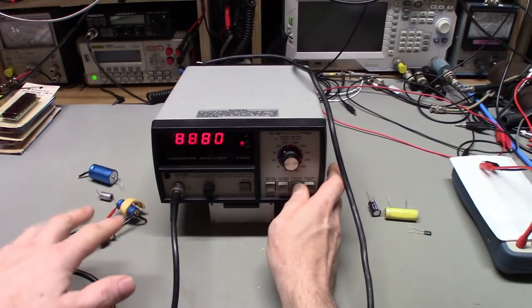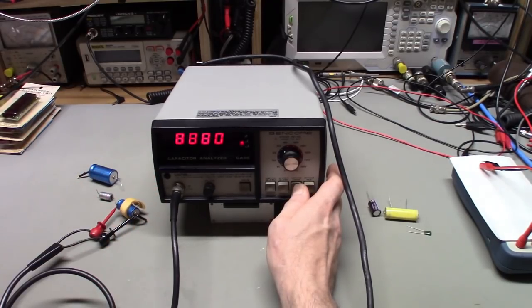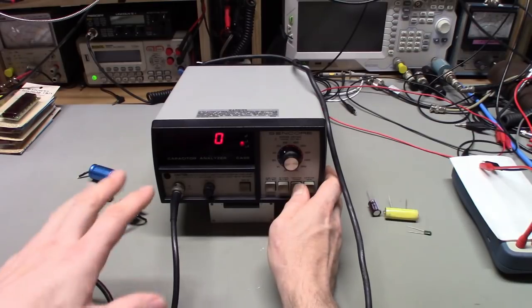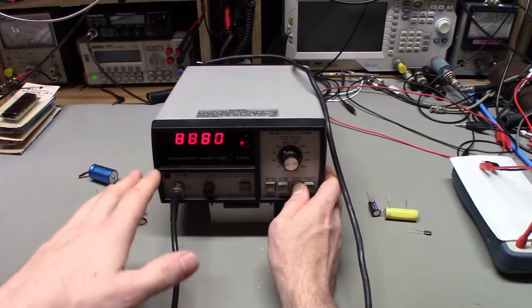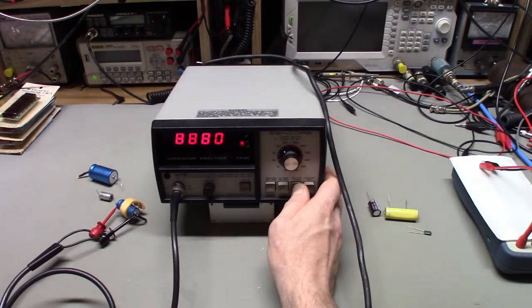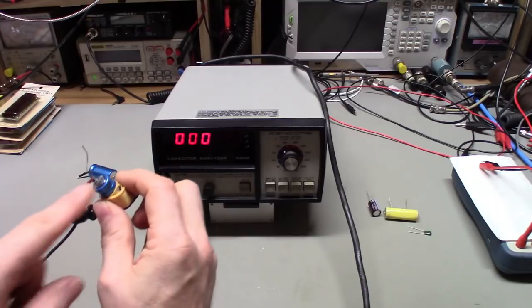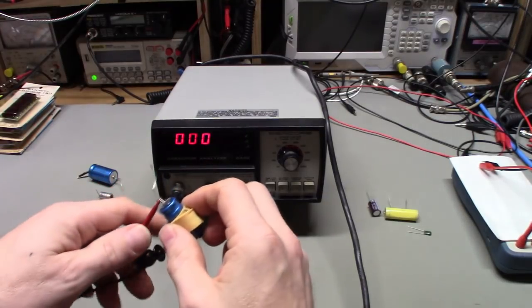I was going to say, this one was actually fluctuating back and forth when I tested it originally. So it's borderline. It's right around that 10,000 microamp leakage limit, so it's tripping in and out, but it's just not charging. It's bad. Again, it's obvious physically. You can just look at it and see that it's bad.